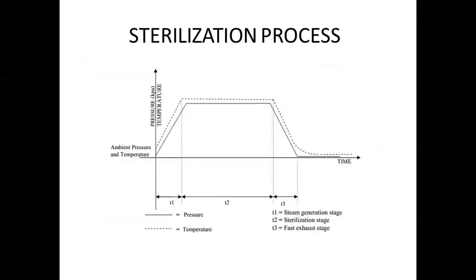So steam sterilization, you can able to see the pressure which is maintained, this line is called the timeline and the ambient pressure and temperature. Okay, this is called temperature pressure couple lines. So where the temperature is present the dotted line, the pressure is present in the straight line. Okay, so T1 is steam generated stage, T2 is sterilization stage, T3 is fast exhaust stage.